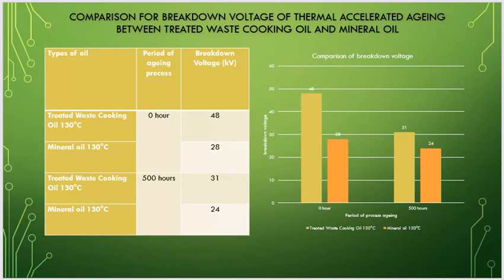Then comparison of breakdown voltage: at 0 hour, treated waste cooking oil is 48; at 500 hours, treated waste cooking oil is 31; and for mineral oil at 0 hour is 28, and mineral oil at 500 hours is 24.